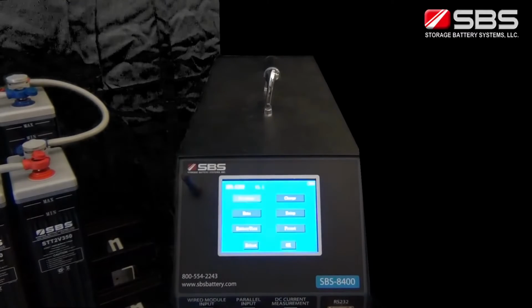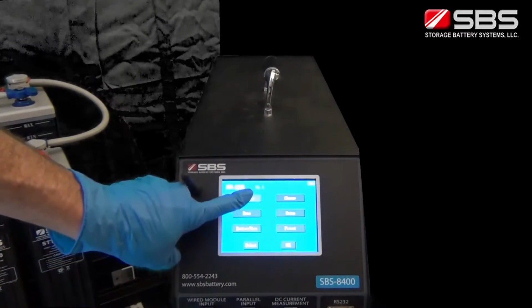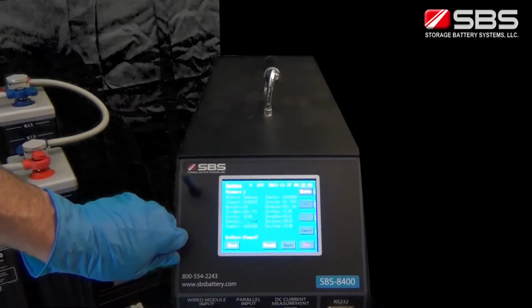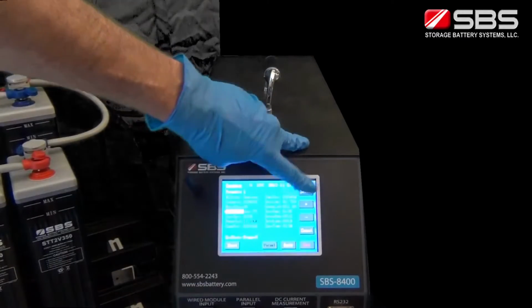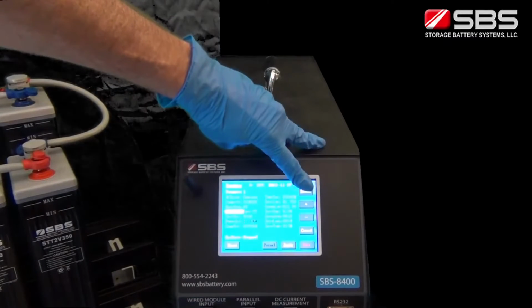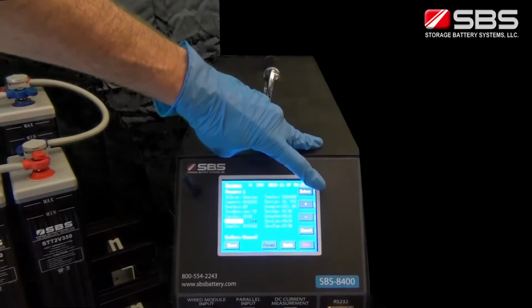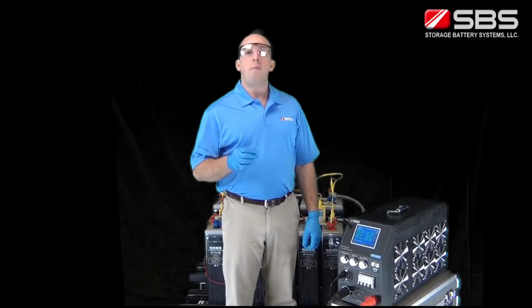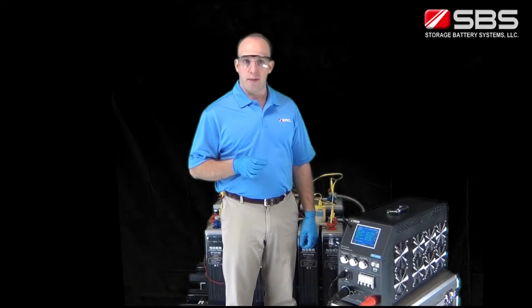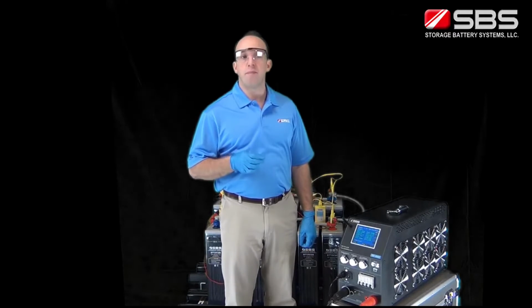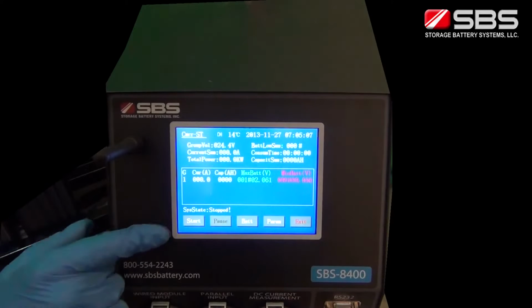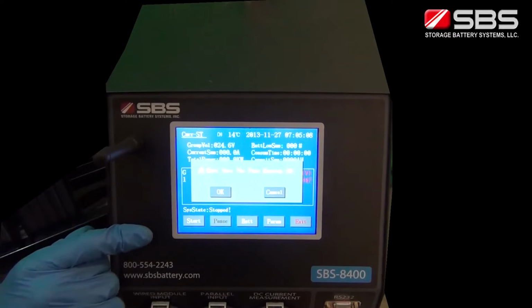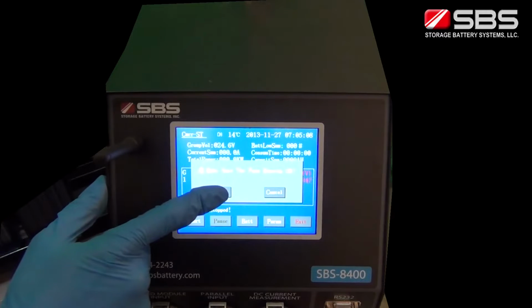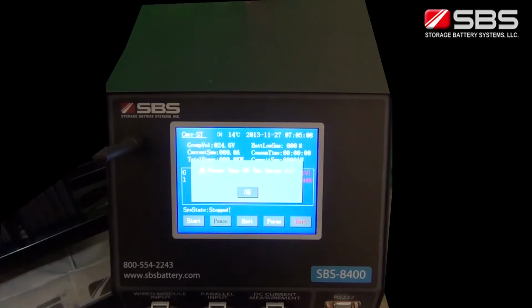A welcome screen will appear. Touching anywhere on the screen will bring up the main menu. Press Discharge in the main menu to enter the parameter interface. You can enter the parameters here and select Apply to save them. Up to 8 preset discharge profiles can be saved and reused for tests of the same type and quantity of batteries. Press Start to enter the discharge interface, and then press Start again to begin discharging the battery string.